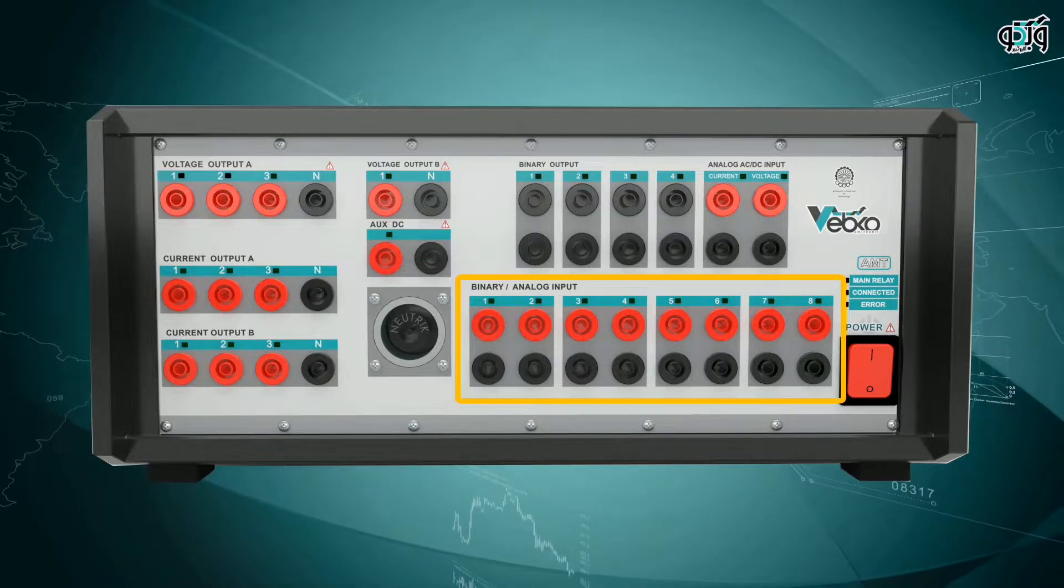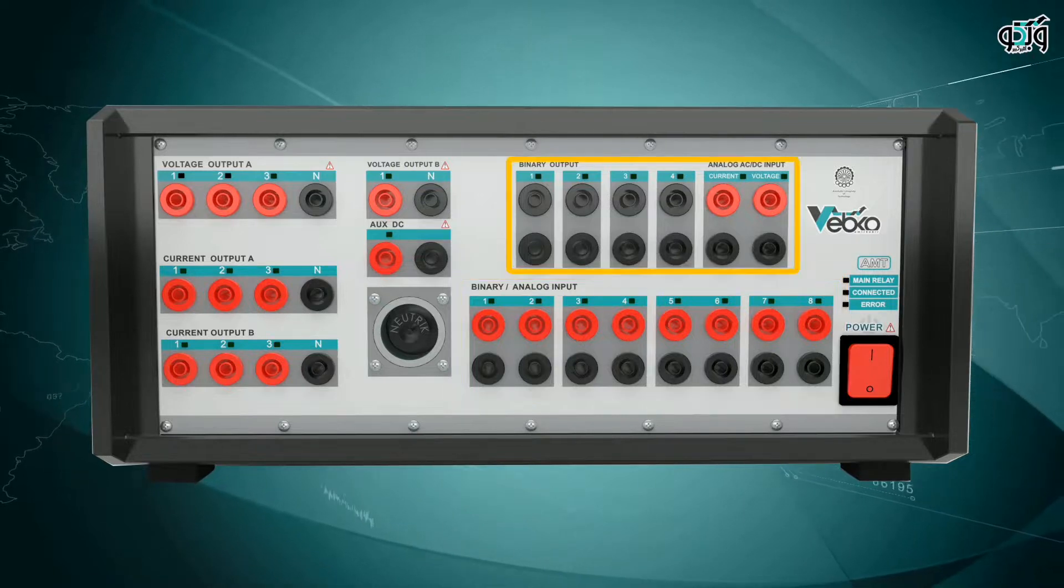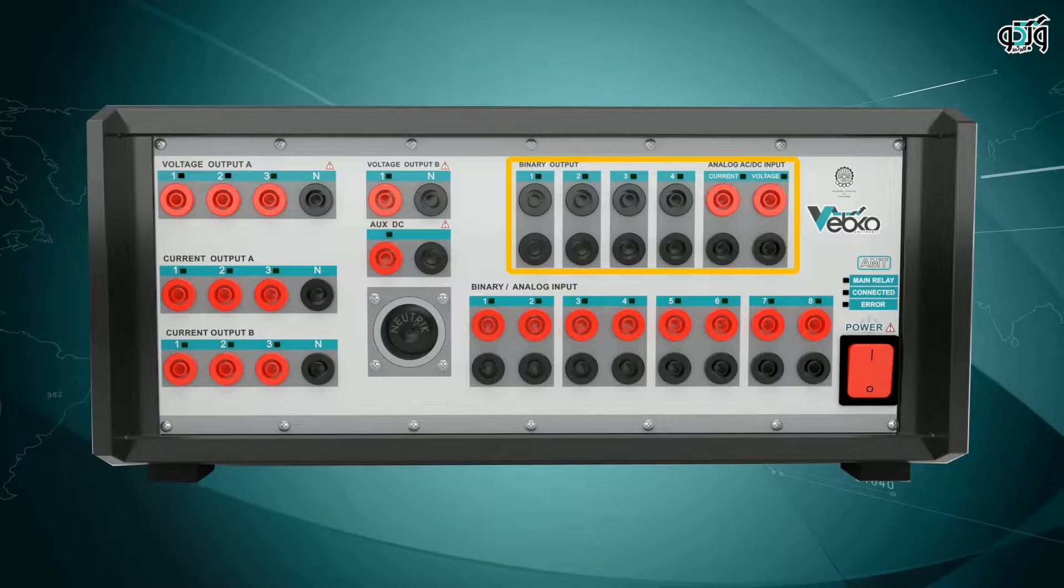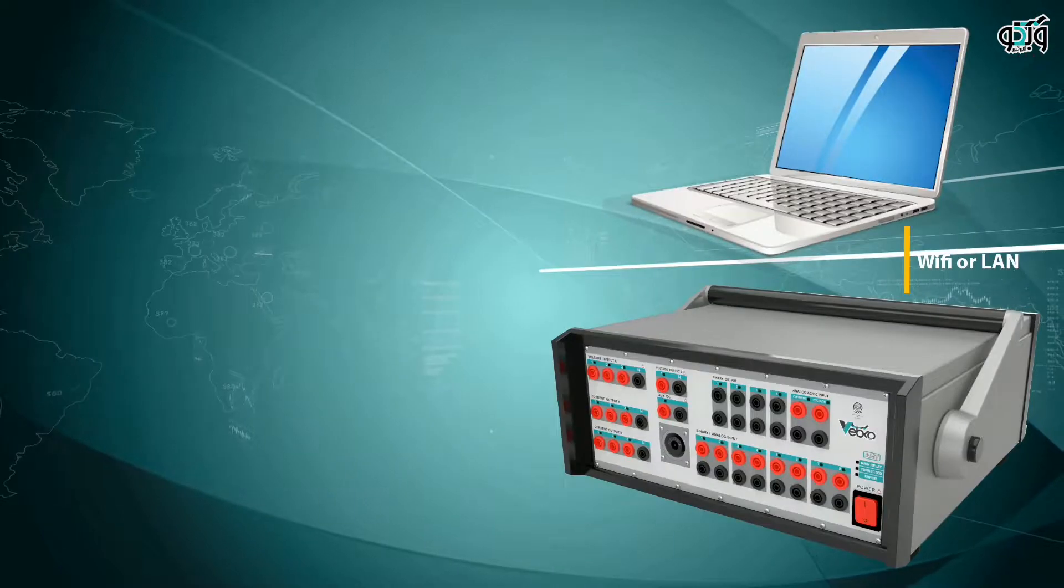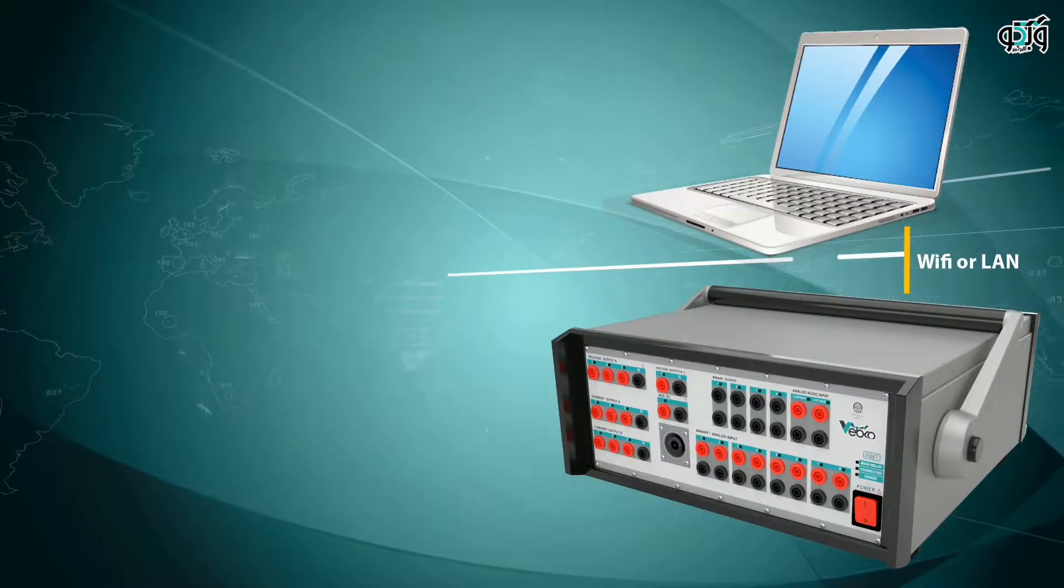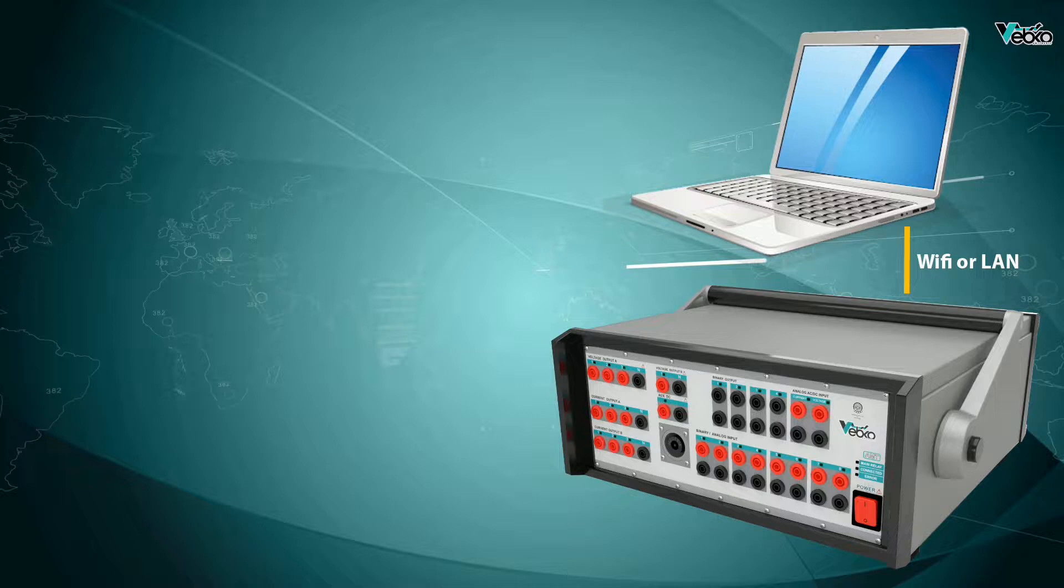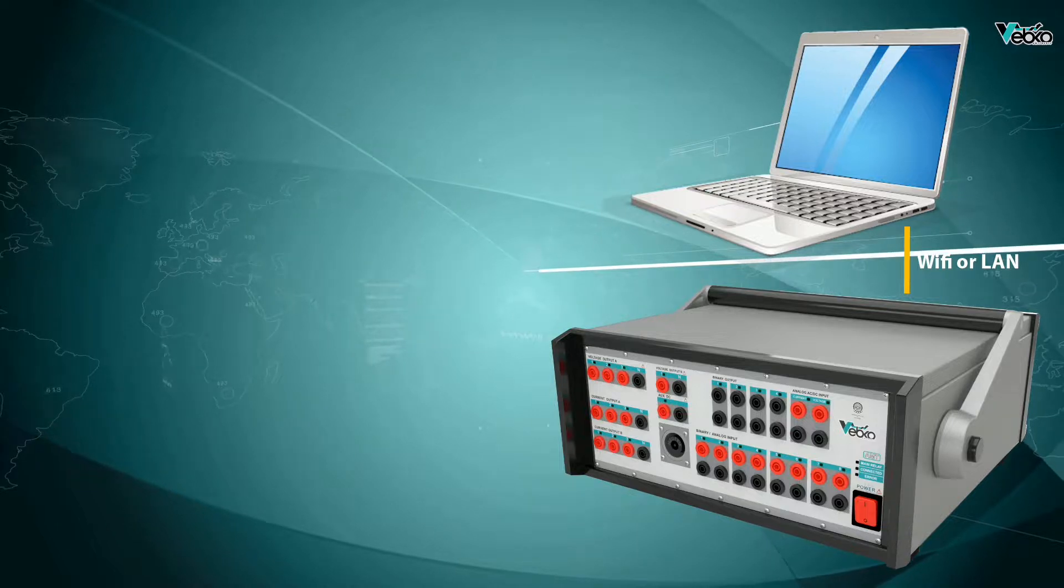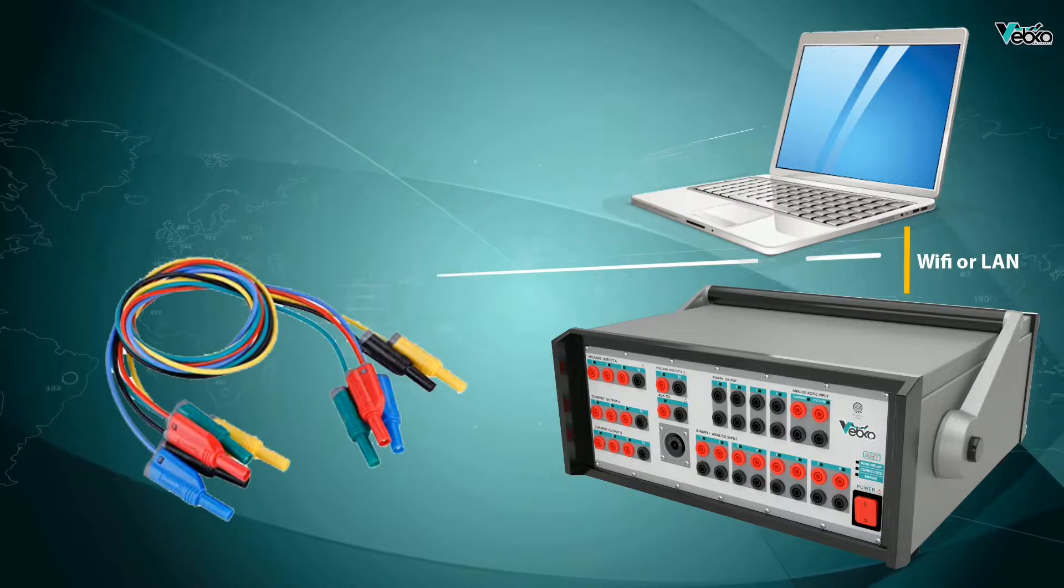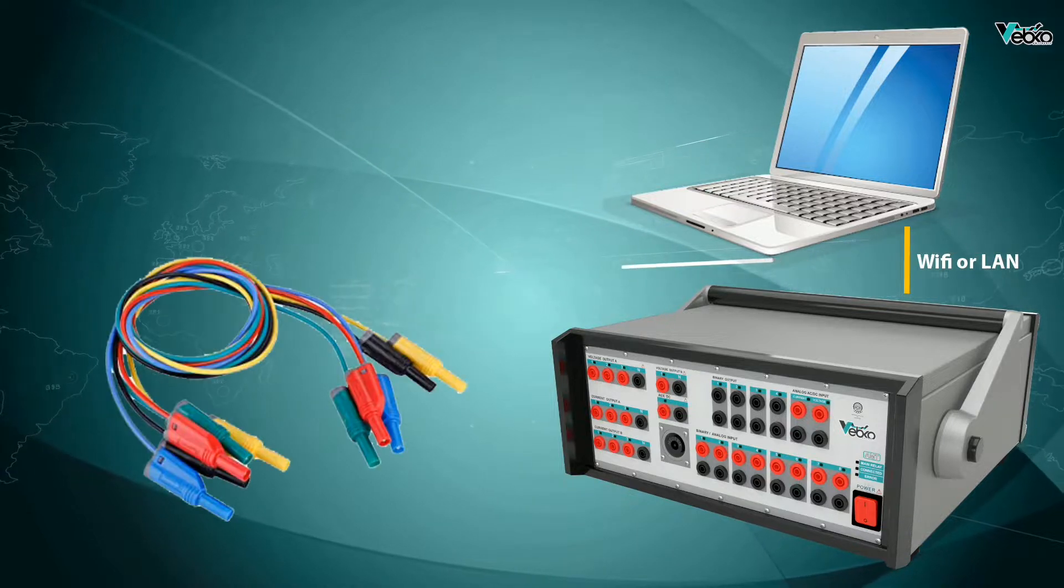Binary outputs can be used in cases such as circuit breaker status or simulation. In the next step, the test device voltage and current injection cables should be connected to the relay or test block to replace CT and PT for injecting the desired amounts.